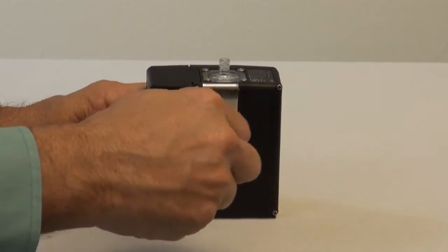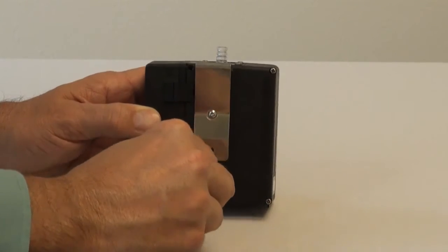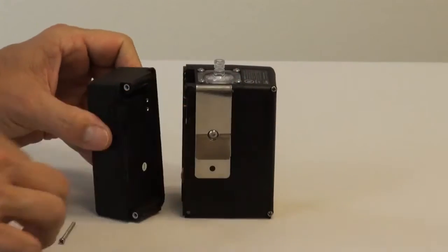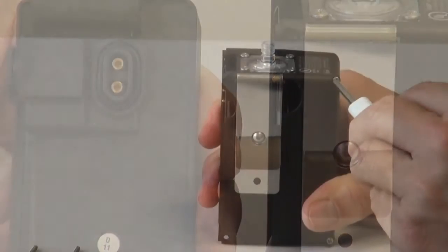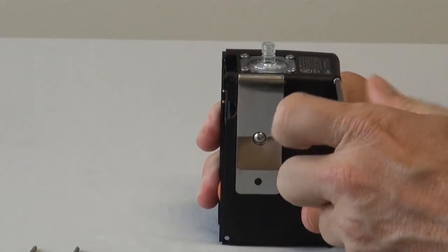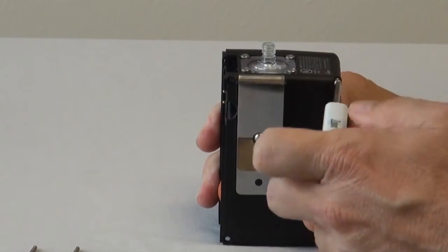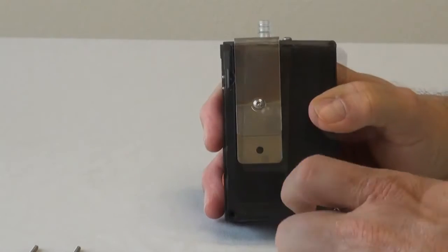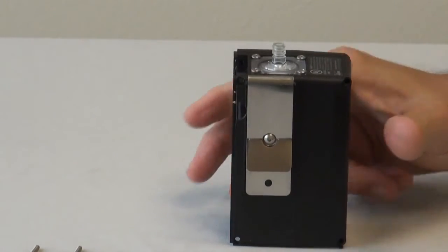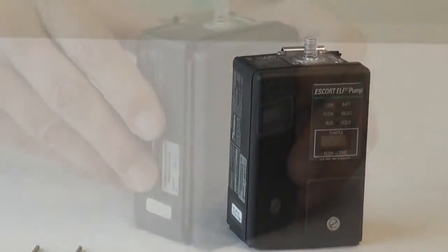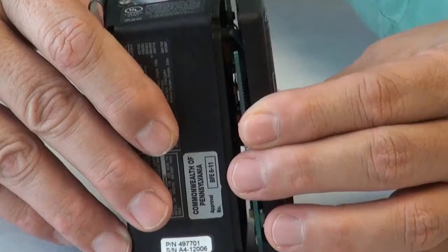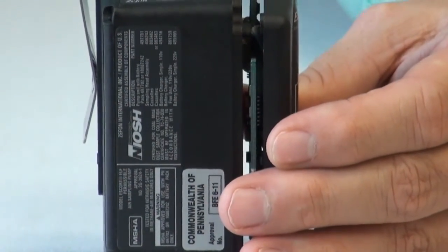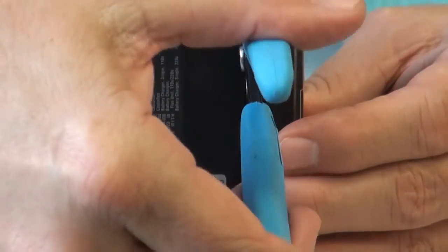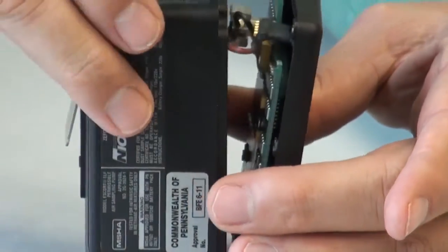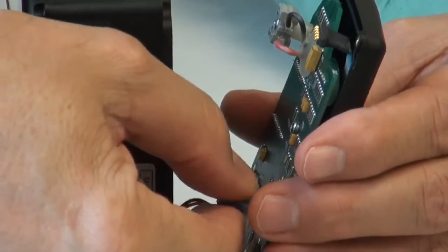To replace the battery pack, remove the 2 screws securing it to the case. Always visually inspect for proper placement and damage of the battery pack O-ring. Now to remove the faceplate, unscrew the remaining 2 screws. As you pull the faceplate away from the case, use a pair of small pliers to gently pull the ribbon cable away from the flow sensor connection. Then unplug the motor connection.